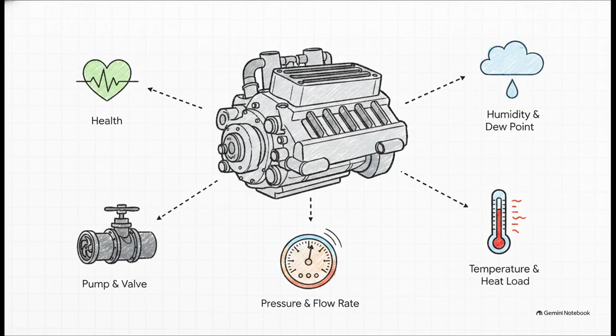Now, you might be wondering, how does the software actually get all this info? Well, for the high-capacity units, like your 100 kilowatt or your EIA and OCP 250 kilowatt in-rack CDUs, SCC retrieves this sensor reading data in real time using the Redfish API.